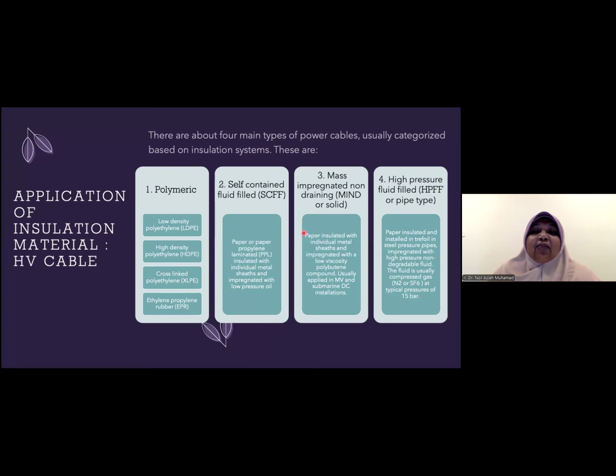So there are four types of cable in high voltage power as a power cable. They are categorized based on their insulation system. First, there are polymeric cables. We have low density polyethylene, LDPE. We have high density polyethylene, HDPE. We have cross-linked polyethylene, which is XLPE. We have ethylene propylene rubber, EPR.